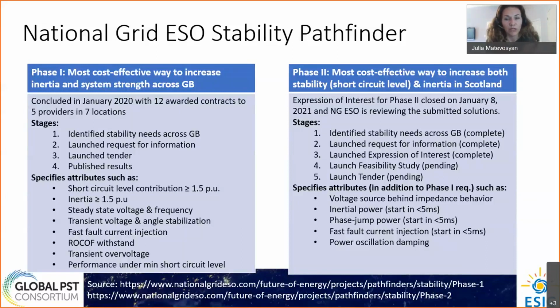Scotland on the grid. And here, the first Pathfinder was restricted to traditional technologies, so synchronous generators and synchronous condensers could participate, and it was awarded to 5 synchronous condensers in 7 locations. Whereas in the second stage of Stability Pathfinder that's going on right now, even inverter-based technologies are allowed to participate.